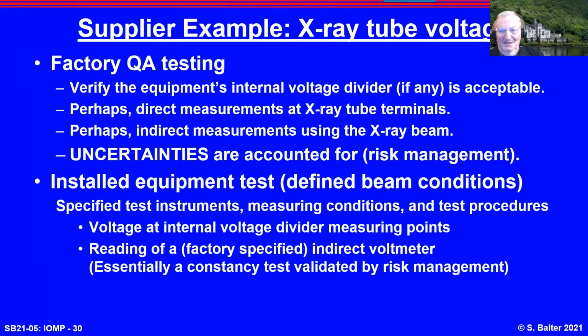So let's go back to tube voltage for a minute. Some of the things they're doing, equipment may have an internal voltage divider. The voltage divider will be tested. They may do direct measurements with their standard voltmeter at the tube terminals. They may do indirect measurements. Again, their process is in the risk management. They have their internal threshold.